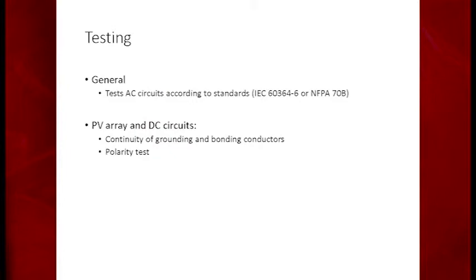Testing all the circuits to the standards for electrical testing and the fire protection code testing. Continuity of grounding and bonding, people, that is very important. Test polarity before you fire these things up.